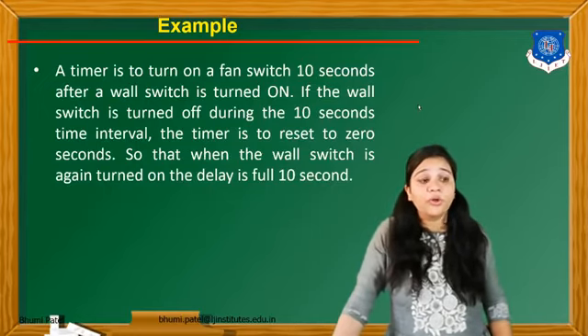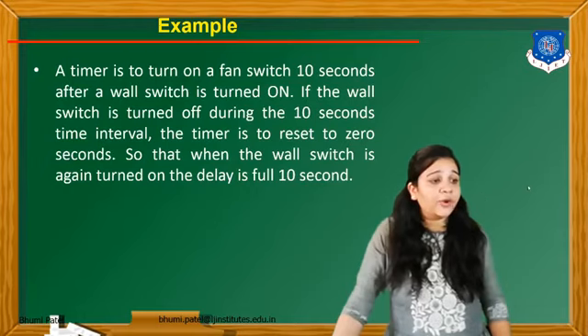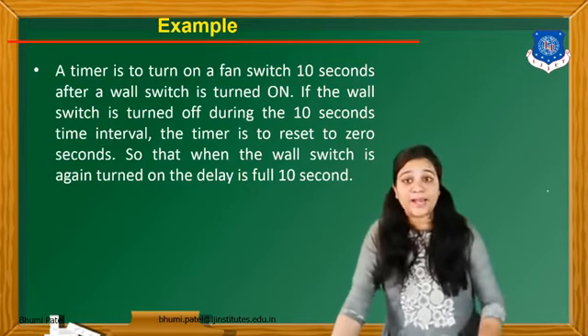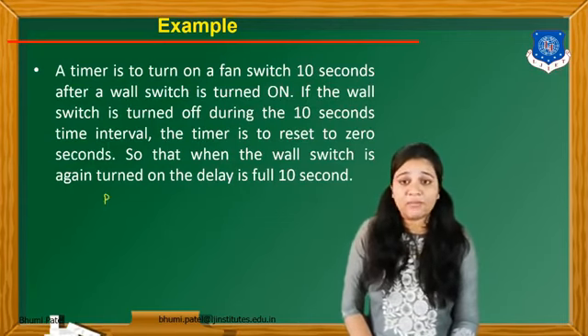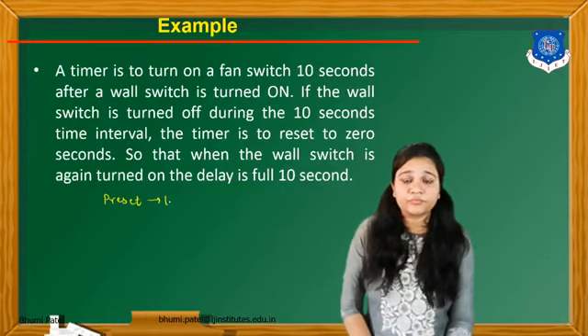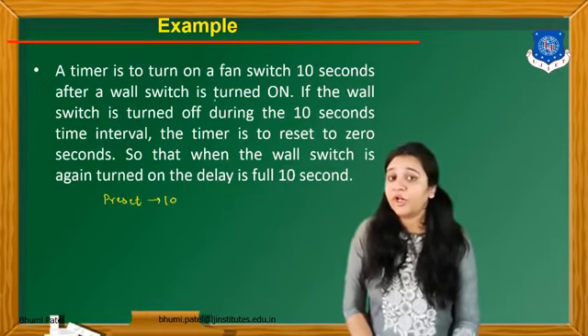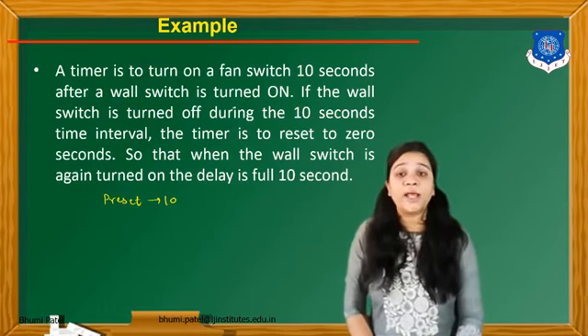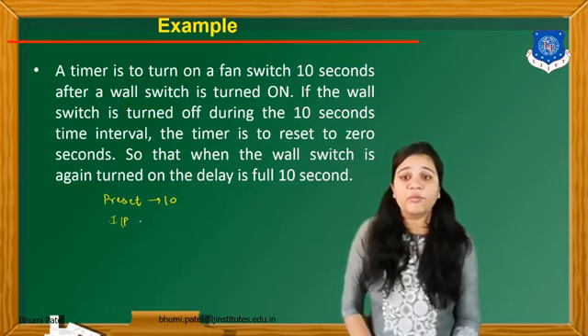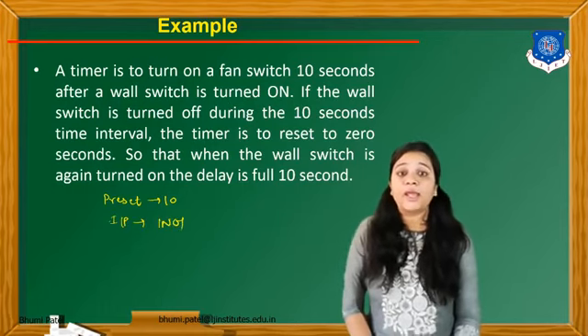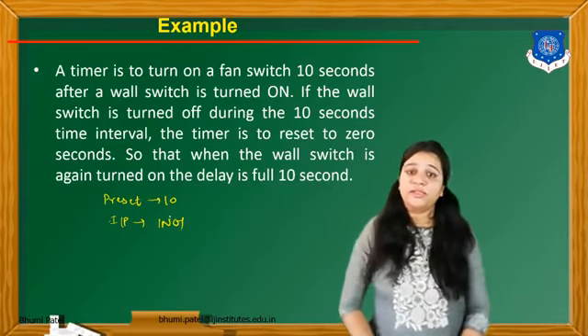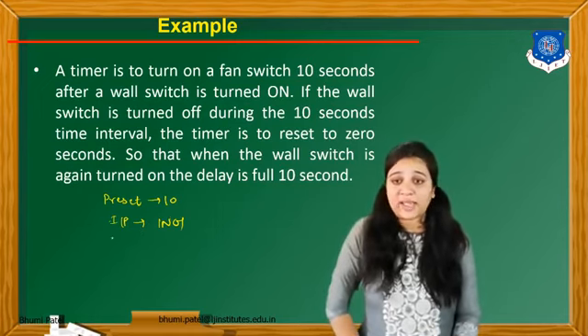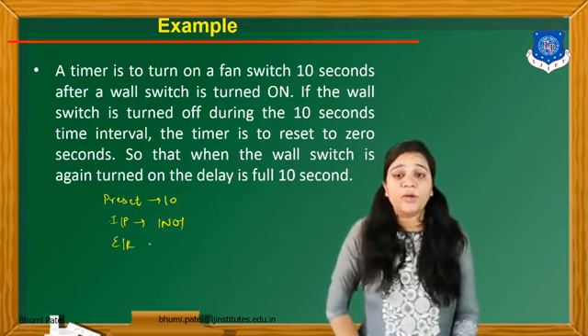So first of all, we have to identify the inputs and outputs for this particular system. The timer is to turn on the fan switch after 10 seconds, so we have to take the preset value as 10 seconds. Now the wall switch is our input signal — we can name the input IN01. And if the wall switch is turned off during the 10-second time interval, the timer is to be reset to 0 seconds. So the key condition is that we connect the enable or reset pin for this particular timer timing diagram.